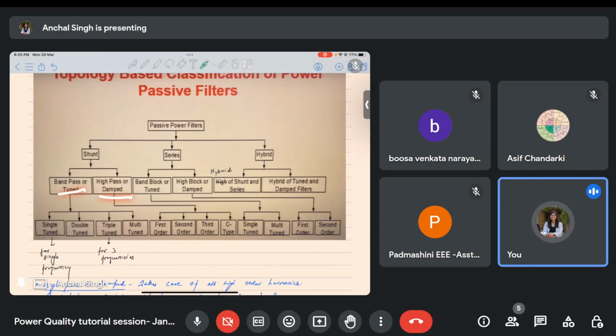Depending on the application, on what harmonics are present in your load current, you decide which one to go for. Then when you're tuning, you could go for either a single tuned or a double tuned. Single tuned means that if in an application I'm targeting just the third harmonic, it is called single tuned. But if in my application there are third and fifth harmonics, then I will tune for both of them, so it will be called double tuned. Then it might be triple tuned or multi tuned. Depending on whichever is cost effective, the multi tuned one or the high pass or damped one, you figure out which one to go for. The high pass or damped one is categorized into first order, second order, third order, or C type.